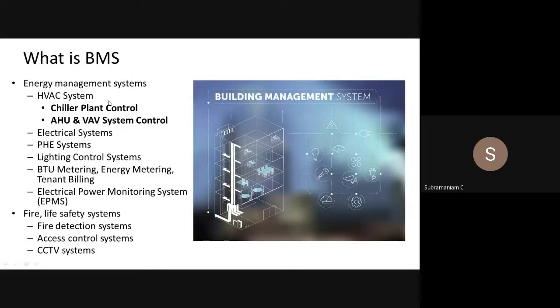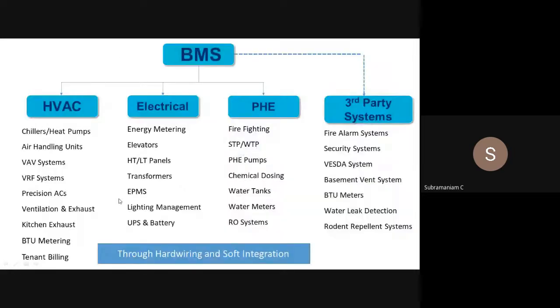One is energy management, that is related to energy. And the other one is non-energy, that is life safety. Because when fire and life safety is coming, we don't talk about the energy part. Whereas energy covers the HVAC system, chiller plant or DX system, VRF system, AHU and VAV control, electrical system, PHE system, lighting control. If it is a tenanted building, if we have 10 floors, a 5 lakh square feet building, and each floor is occupied by a tenant, how do we do BTU metering? How do you bill chilled water consumption like electricity, tenant billing? All that is very important. And we also have BMS where the fire alarm system is integrated. If you want, we can integrate to some extent access control, CCTV, everything, but it all depends on the cost.